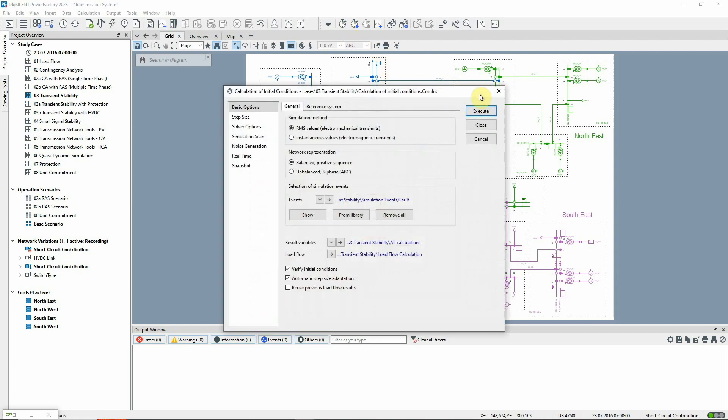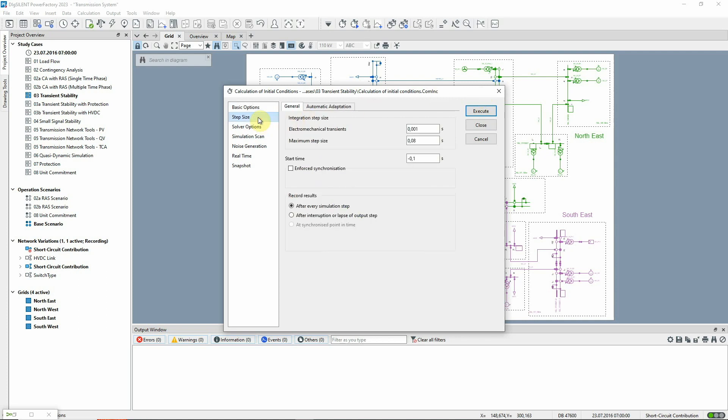If no load flow results are available, a load flow will automatically be run first. We will study a three-phase fault so the network representation is balanced, positive sequence. Other options have already been set, such as the step size and start time.